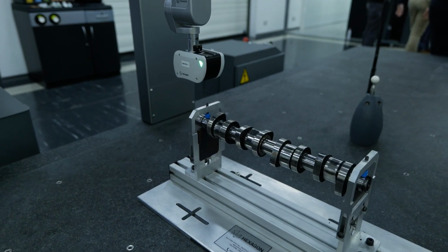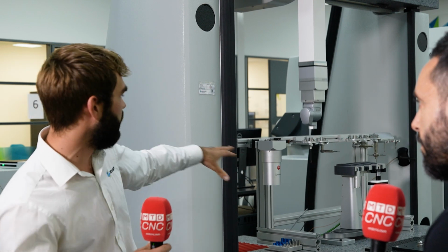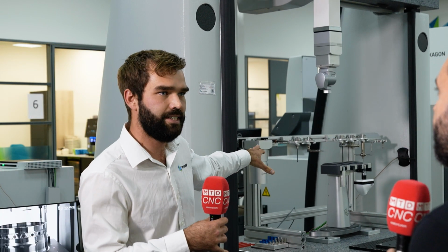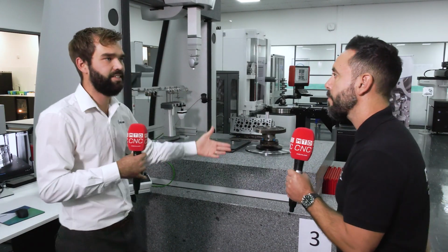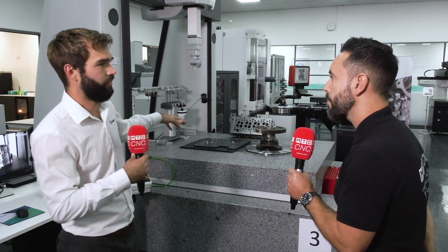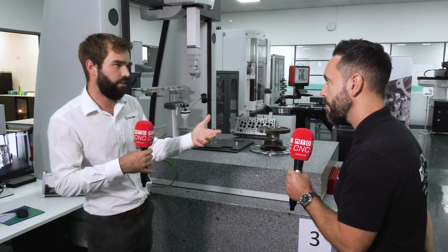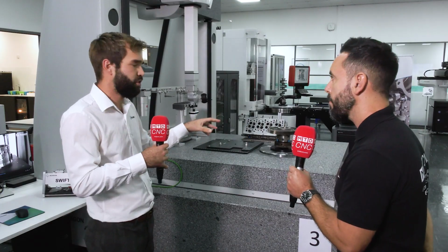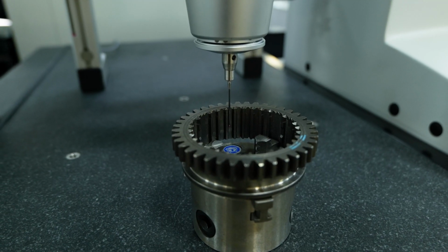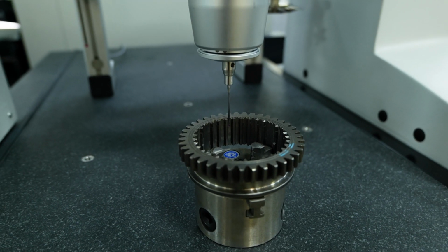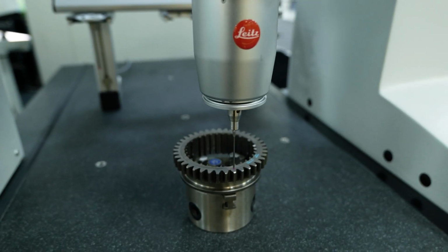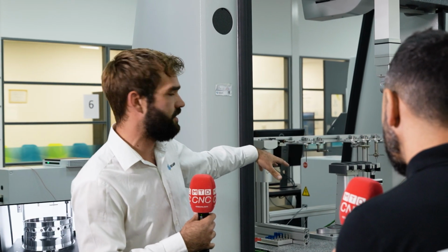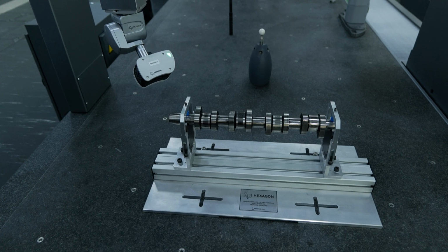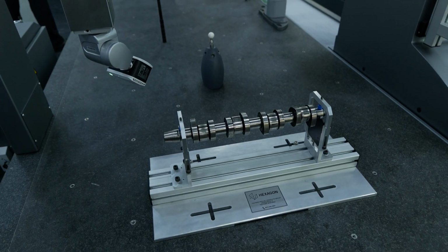So on here, with the different sensors, you can see now it's changing, which we're able to change between different contact sensors, optical sensors, roughness sensors, laser solutions, and we can use those all in combination in one measurement run to get the best out of the machine. So if we take the gear on the machine here, we need ultimate accuracy for that. So we can use the fixed head to conform to the ISO standards that we need for approved gear measurement. But we can also pick up the other sensors like the laser to capture surface and topographic data of that gear that we can use for different purposes.